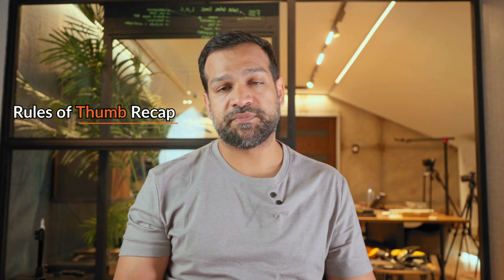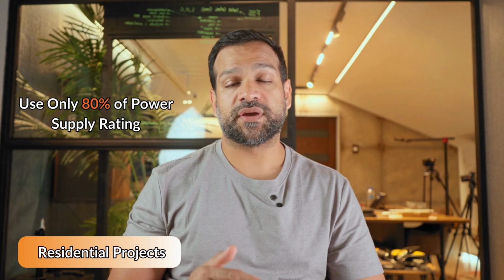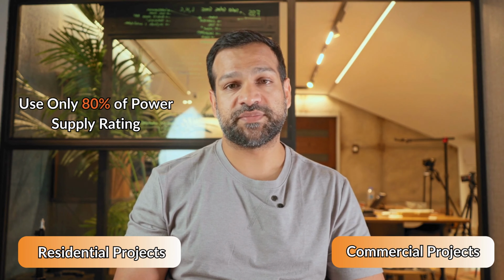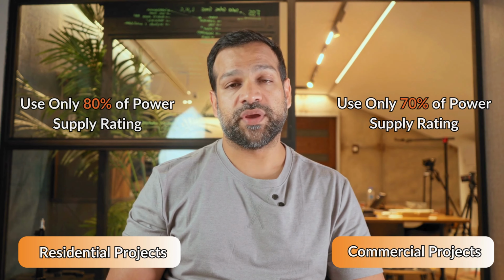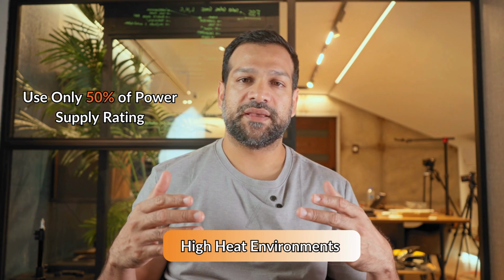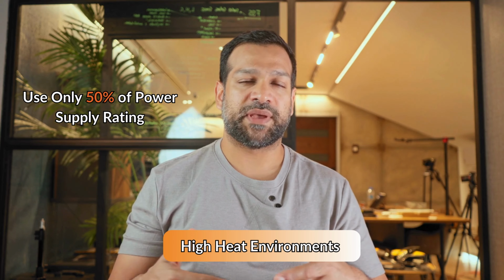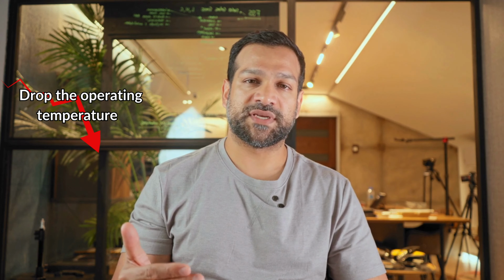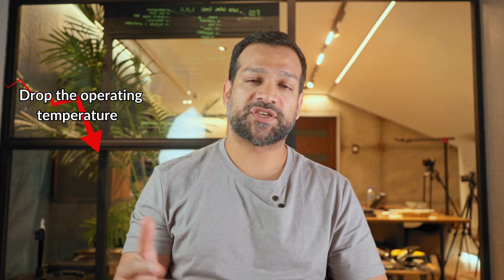If we're doing residential power supplies, we tend to load the power supply only 80%. If we're doing a commercial project, we tend to do only 70% of the power supply's max rating. If we're doing an extended commercial or an environment that has a lot of heat for whatever reason, there might be a lot of machinery or a lot of equipment around generating excessive heat. Like if you put a power supply behind a refrigerator because that was the only available space in that installation, you want to drop the operating temperature of the power supply to compensate for the extra heat being given off by the refrigerator. Even though it's not an ideal situation, it tends to happen.